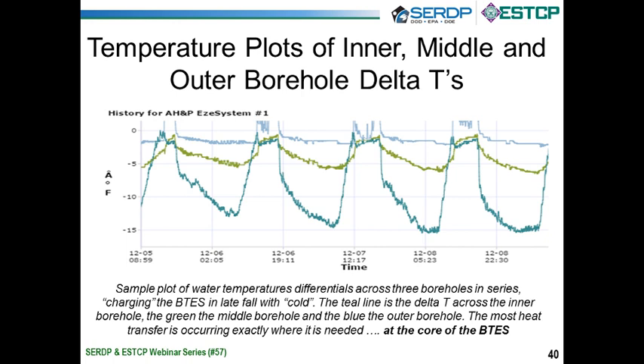As many of you know, low GPM, high delta T leads to low pump energy consumption. So you've got to do the right thing on the inside of the building. But if you go to an average geothermal system with all the piping in parallel, you'll typically see maybe a 6 to 8 degree drop. So we're maybe doubling or tripling that to try to save some energy. So we did truly do the work at the core where we wanted it to be done.